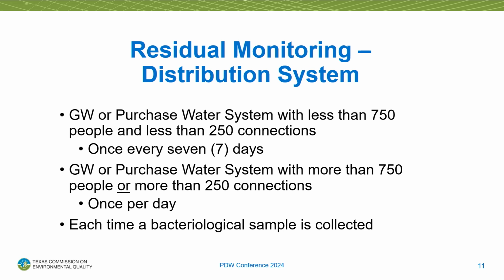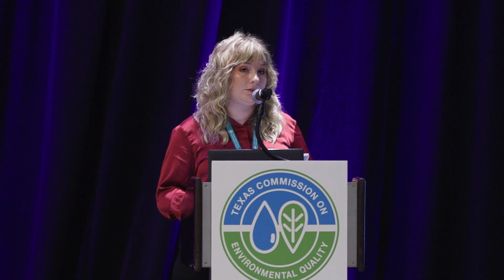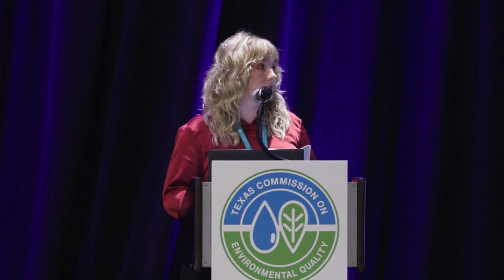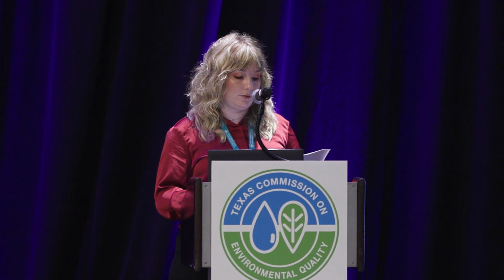This is going to tell you the minimum requirements of how often you're going to take residuals. For groundwater and purchased systems, if you have less than 750 population or less than 250 connections, you're going to be testing once every 7 days. If you've got more than 750 people, and it's important that it's also more than 250 connections, that's going to be daily. So you could have a population that's under 750, but if you've got 256 connections, you're still going to have to do daily residuals.